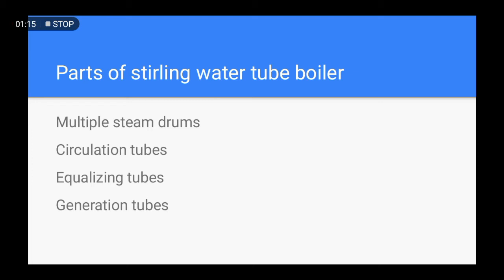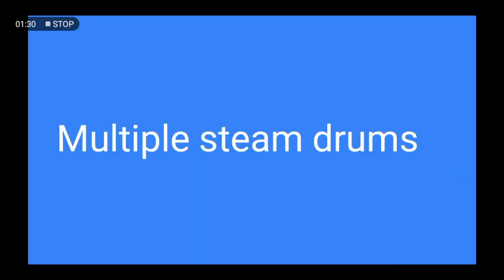The parts of a Stirling water tube boiler are approximately the same as other water tube boilers, but here we will discuss some different parts. The parts are: multiple steam drums, circulation tubes, equalizing tubes, and generation tubes. A normal water tube boiler usually uses two drums — one is the steam drum and the other is the mud drum — but a Stirling water tube boiler uses multiple drums, ranging from three to seven, depending on the boiler size and the quantity of steam required.